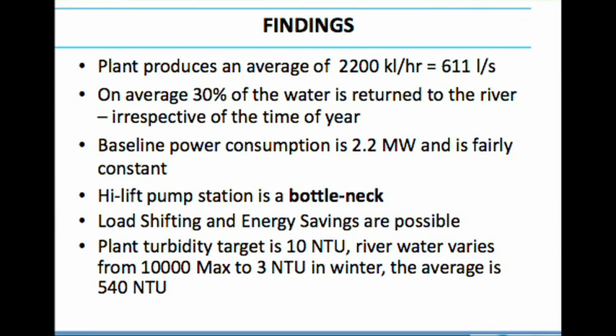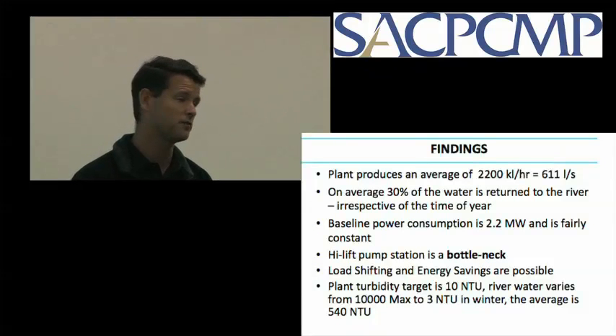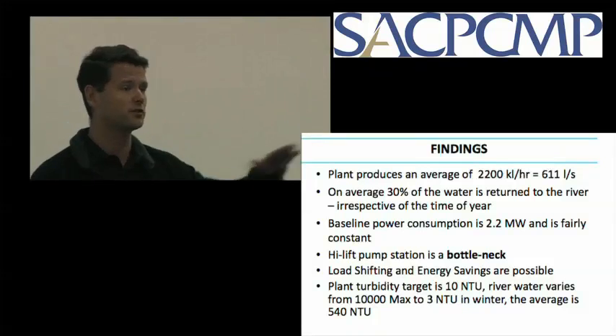So what did we find to summarize? Plant produces about 600 liters of clean water every second to supply the mill. On average, 30% of that water was returned to the river, irrespective of the time of the year. Baseline power consumption was 2.2 megawatts, and it was very constant, which was great from an M&V perspective, because now you're starting with something constant.